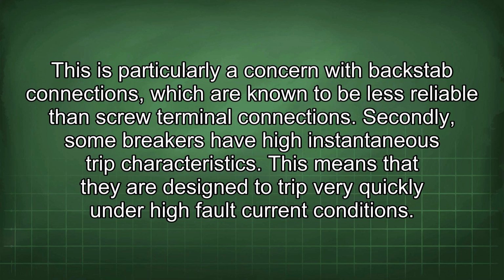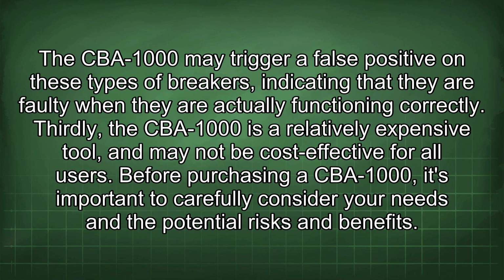Secondly, some breakers have high instantaneous trip characteristics. This means that they are designed to trip very quickly under high fault current conditions. The CBA-1000 may trigger a false positive on these types of breakers, indicating that they are faulty when they are actually functioning correctly. Thirdly, the CBA-1000 is a relatively expensive tool and may not be cost-effective for all users.